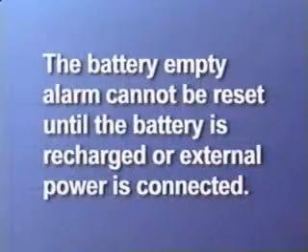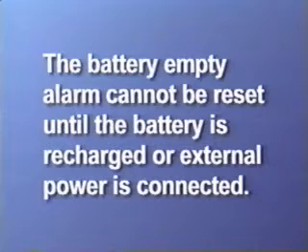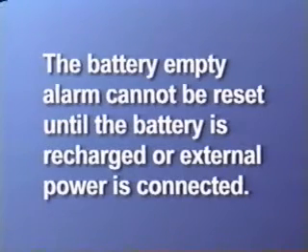Actual running time may be more or less depending on the settings, patient demand, and battery age. To temporarily silence the battery empty alarm, press the silence reset button. The battery empty alarm cannot be reset until the battery is recharged or external power is connected.